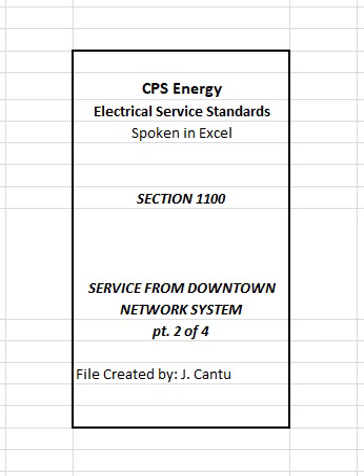H. Doorways. If the design includes a doorway, then the customer shall provide doorways as specified by CPS Energy's Network Engineering section. 1. A minimum of 2 4-foot W by 9-foot H side-by-side doors leading into a transformer room from the building exterior shall be provided. Doors shall be designed to swing out 180 degrees with no external obstructions and be tight-fitting metal fireproof doors having a minimum 3-hour rating. CPS Energy will install a continuous 6-inch removable brick sill.